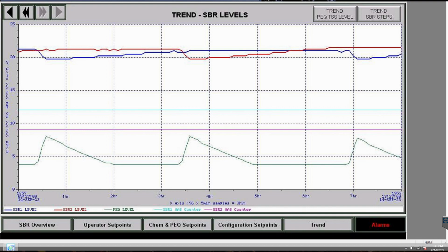Well, our decision in the software says we're going to allow the operators to put a buffer in there above top water level to say, as long as we're within that buffer, we're going to still keep putting influent into the tank that's in fill rather than switch and put it into a tank that's in settle or decant. And that buffer is defined by your software top water level. I'm sorry, software emergency top water level. So if you've read through the literature, you've probably seen reference to an emergency top water level set point.